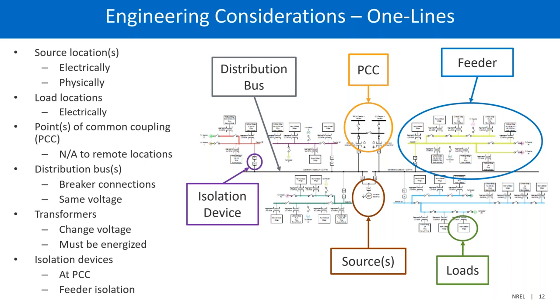And you look at the figure on the right. So the point of common coupling for this particular system is in the center. There are a couple of different distribution buses. And then a lot of times, where the load is situated are called feeders. So you have multiple feeders coming out of the distribution bus, and those feed typically different sections of a facility. So you might have a neighborhood being fed by one feeder. So that's an idea of what the one line would look like. All right, next slide.